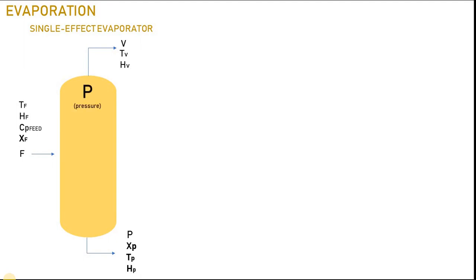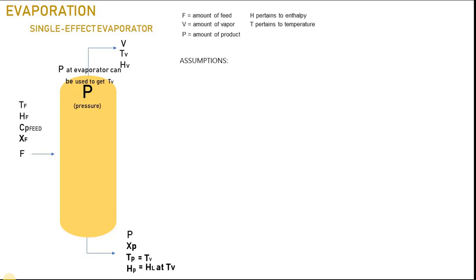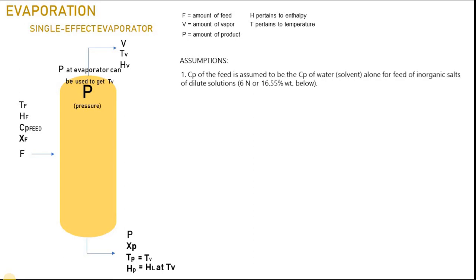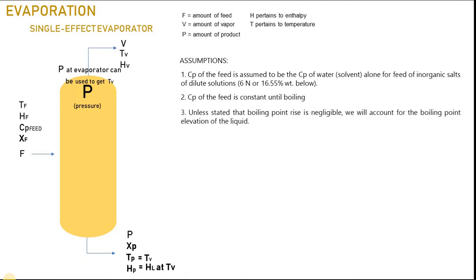The working pressure of the evaporator is defined and is denoted P. In solving evaporator problems, we have to make some assumptions to simplify our calculations. Please take note of the following assumptions because this will be our basis in solving. The heat capacity of the feed is assumed to be the heat capacity of the water in the feed alone, for feeds of inorganic salts or dilute solutions.